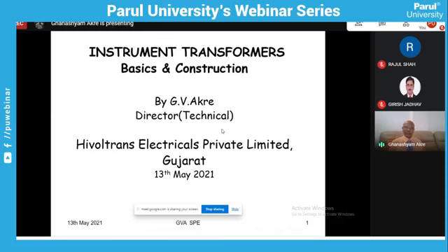So this transformation from high voltage to low voltage and from high current to low current is done by the instrument transformers. These transformers, you can understand, have to be very, very accurate. Secondly, they should have a full life of 25-30 years and be capable of protecting everything. Their quality has to be such that they themselves do not fail, because being transformers filled with oil and subjected to the environment, they can fail. But the quality of these instrument transformers particularly has to be very, very high.